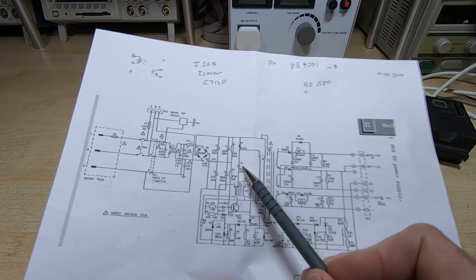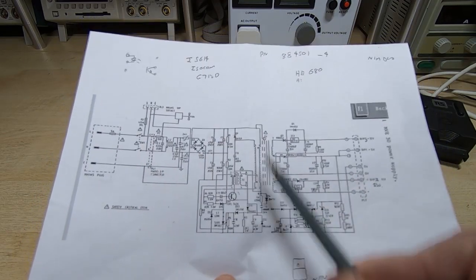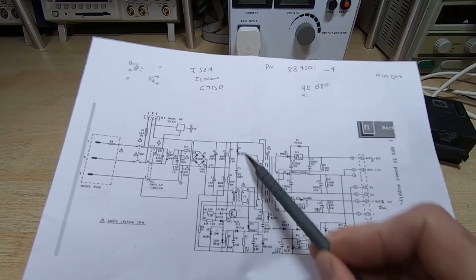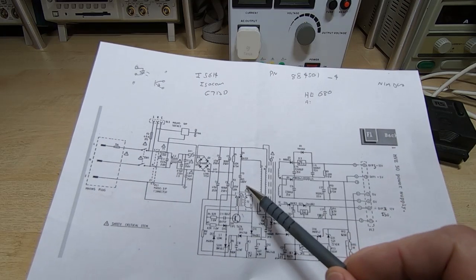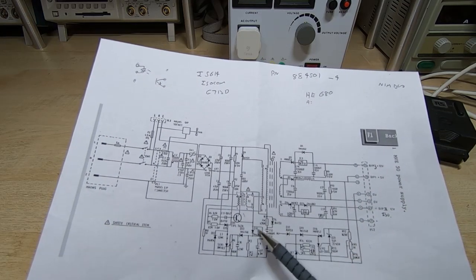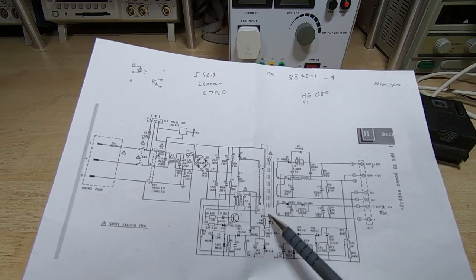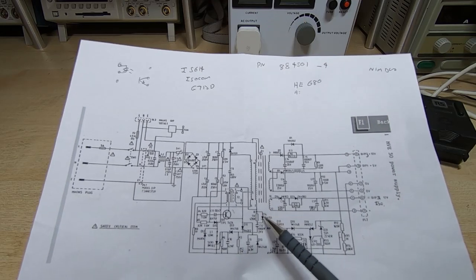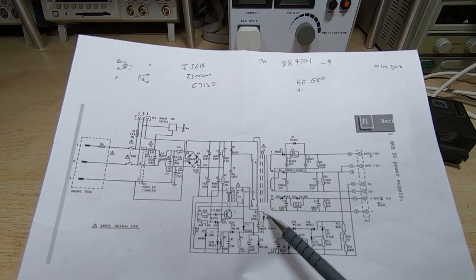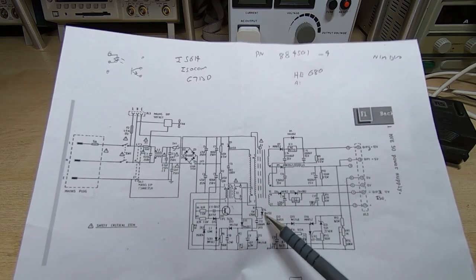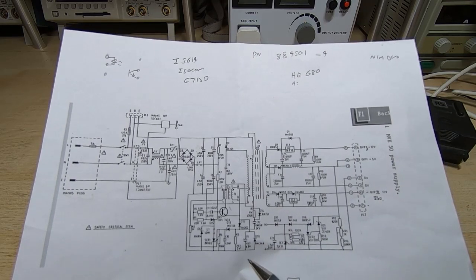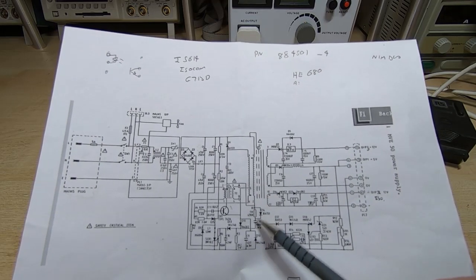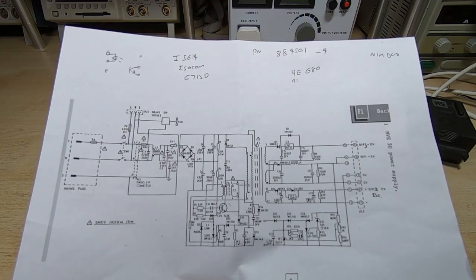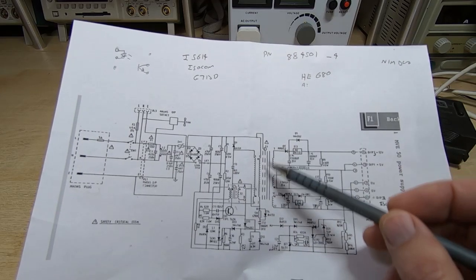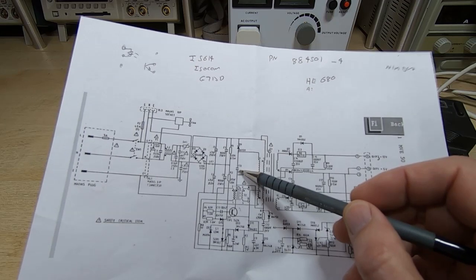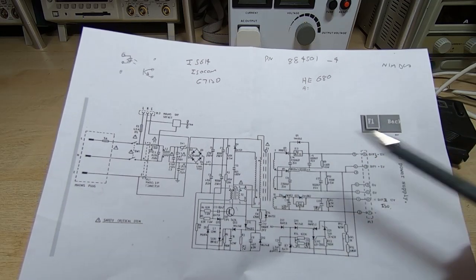Normally it's something very simple, and you can identify those on the diagram fairly easily, which again is why I was using this diagram. Although it's different from this, it gives me an idea as to the type of architecture we're looking at. So this is an example of a snubber circuit, and we have in this example snubber circuits for switch on and switch off. What they normally consist of is a resistor, a diode and a capacitor. The idea is that the diode and the capacitor kind of take over the current path, and the value chosen for the capacitor determines how long current can flow in that process. And then you get the reverse going the other way. This capacitor and this resistor are part of the chopping system for this particular supply.